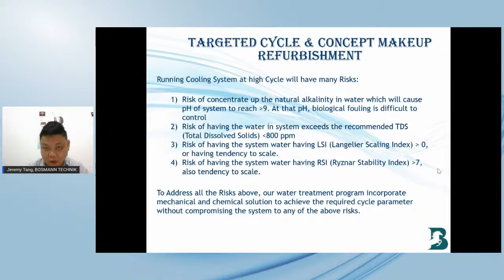The second risk is having the water in the system exceed the recommended TDS, the so-called total dissolved solids, of more than 800 ppm. It will cause a lot of scaling in the system piping. There is also the risk of the system water having an LSI more than 0, which is a tendency to scale, and an RSI more than 7 is also a tendency to scale. So to address all the risks above, our water treatment program incorporates mechanical and chemical solutions to achieve the required cycle parameter without compromising the system to any of the above risks.